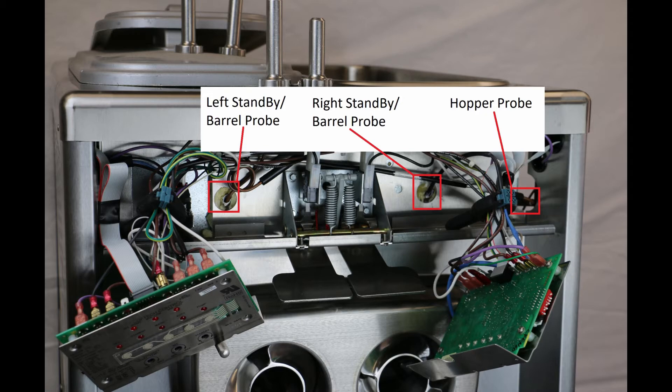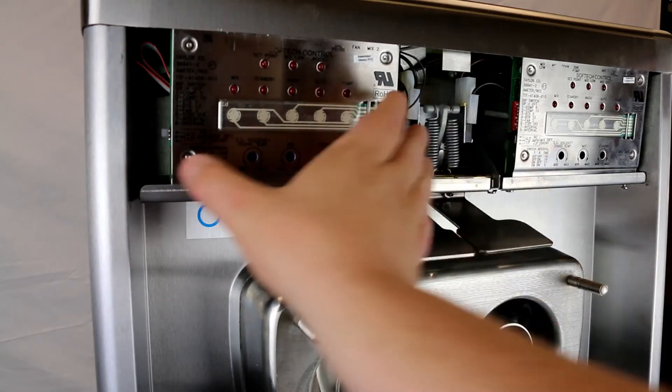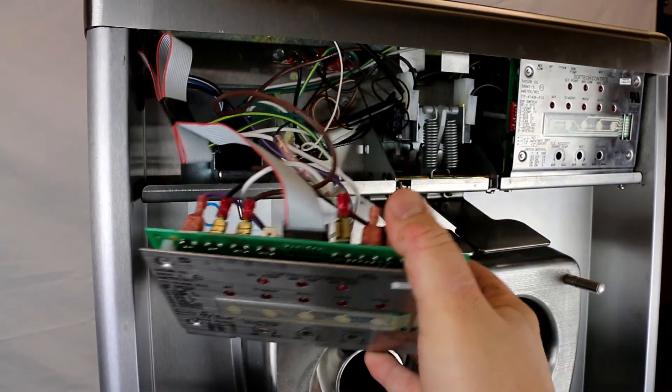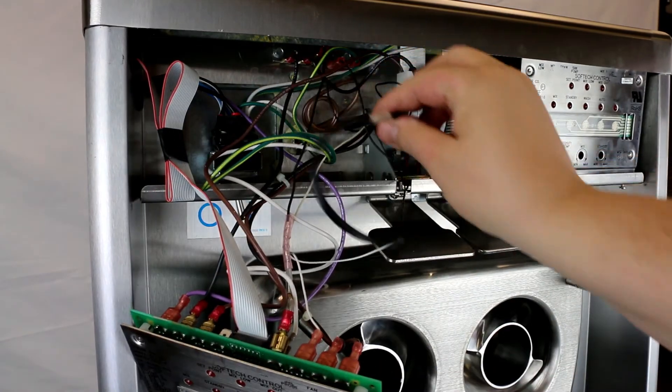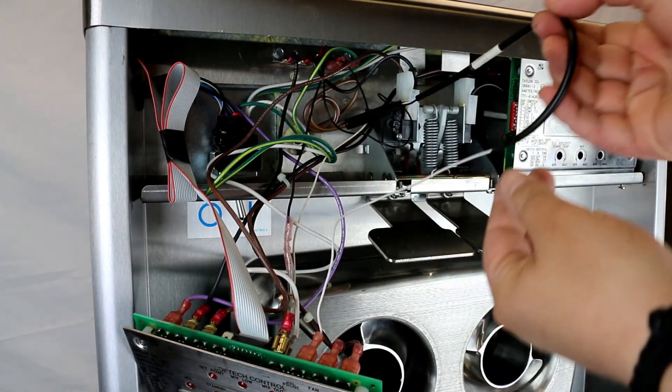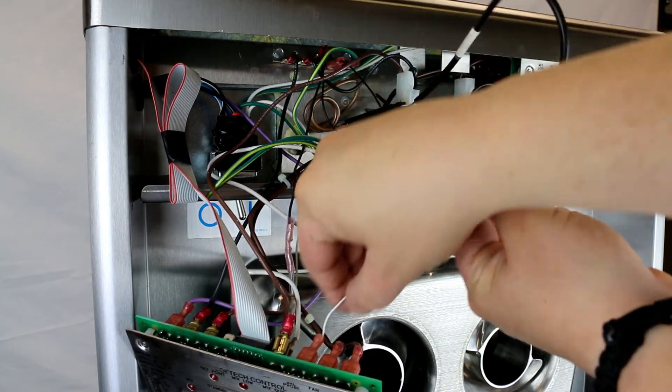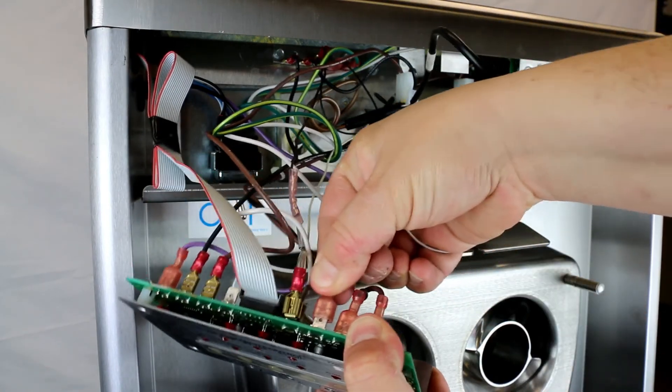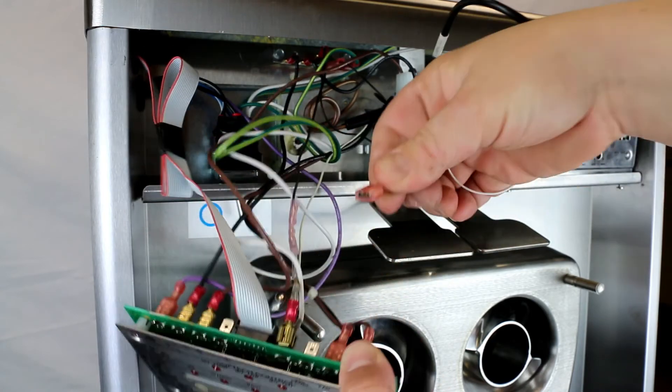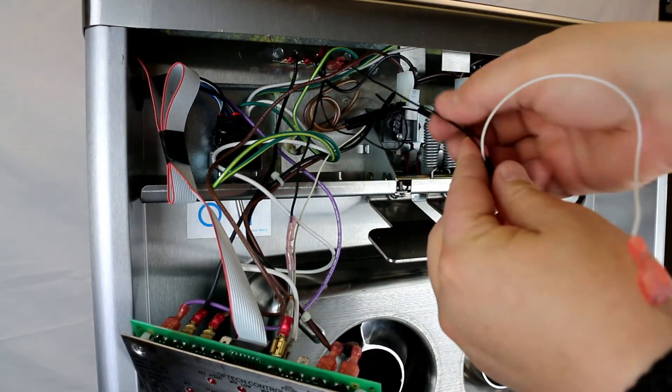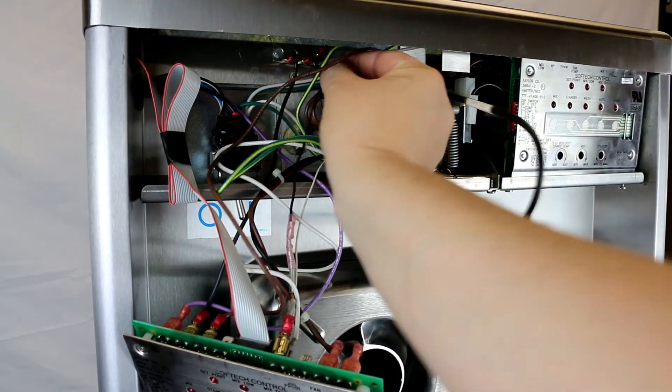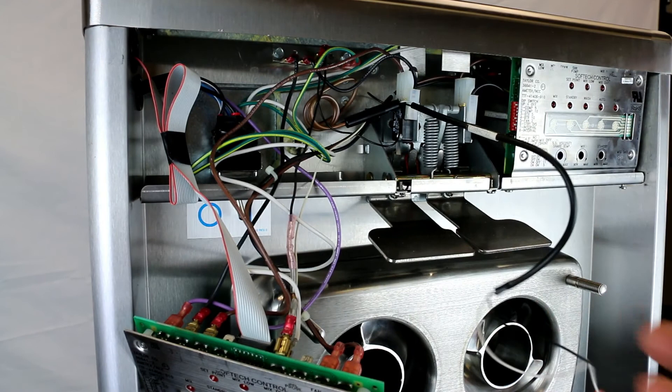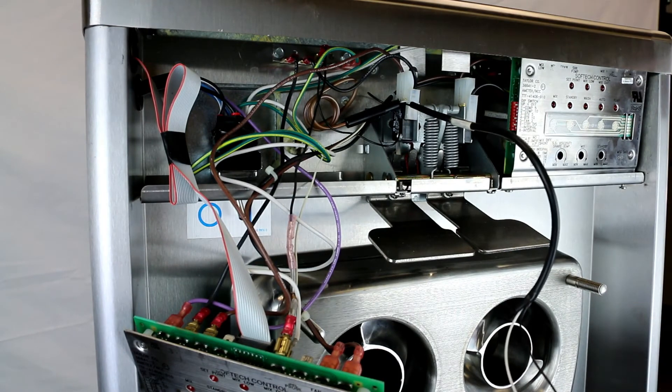We check a thermistor probe by measuring its resistance. On my meter I'm going to set it to ohms. If you have a selectable multimeter, it needs to be set to 1K ohms. You can start by removing the leads to the probe - should be a black and a white wire. The colors really don't matter. One wire goes to the logic board, the other connects to a ground. We're going to disconnect those and connect the leads to our meter.